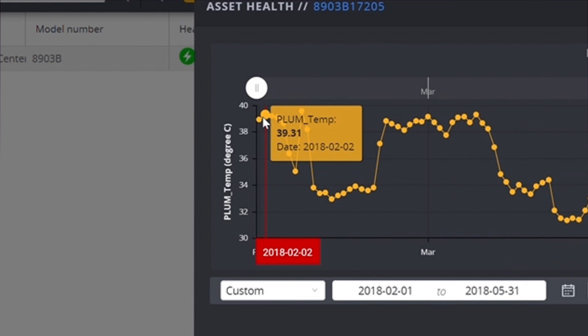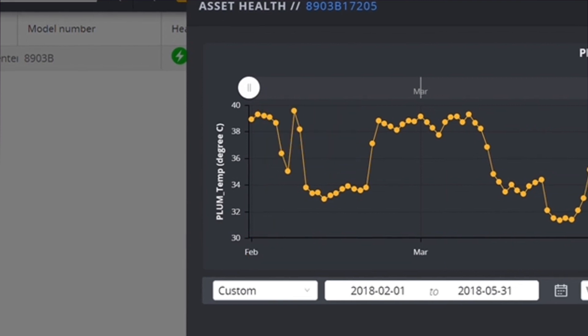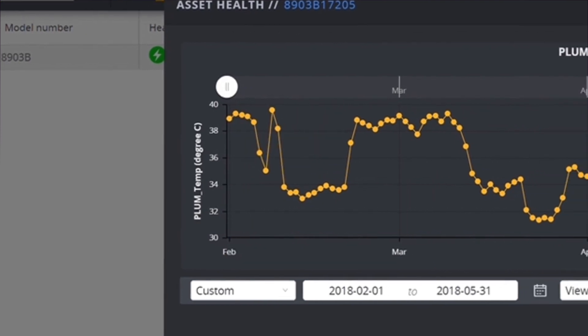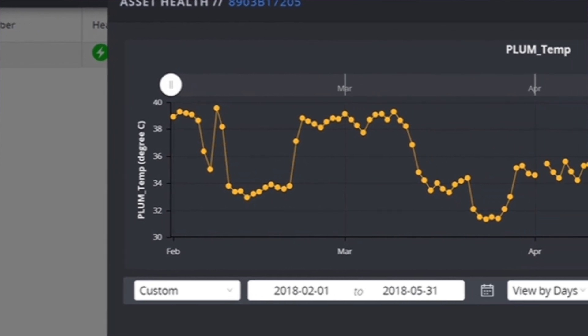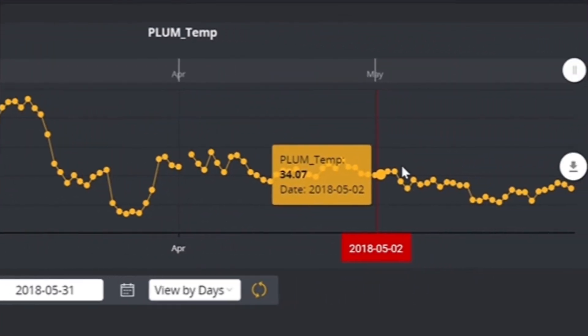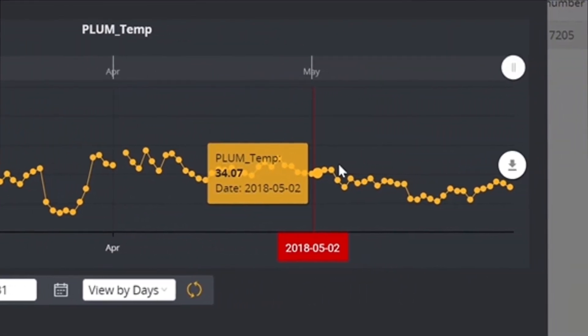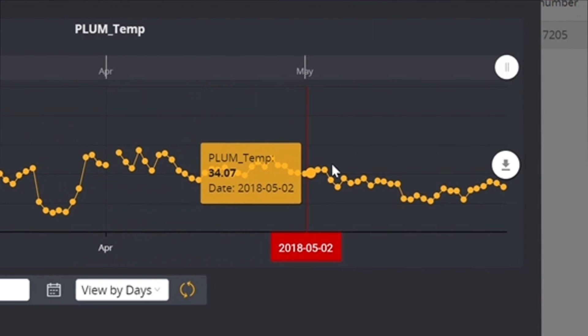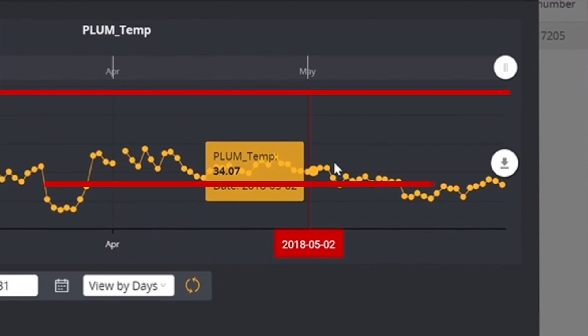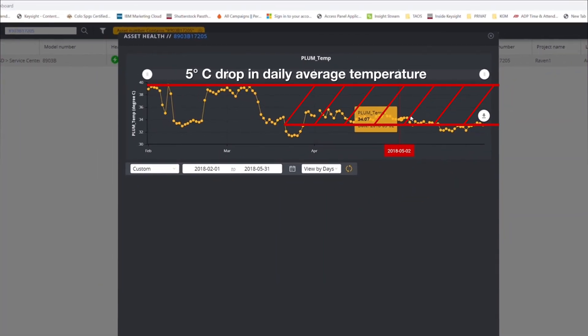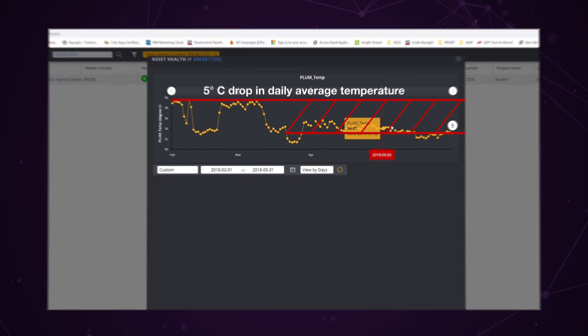For this instrument, temperatures were as high as almost 40 degrees Celsius. The data enabled you to mitigate the situation. In this case, your team moved the rack and added fans to increase ventilation and circulation, which permanently reduced temperatures by 5 degrees. Potential failure and downtime avoided.